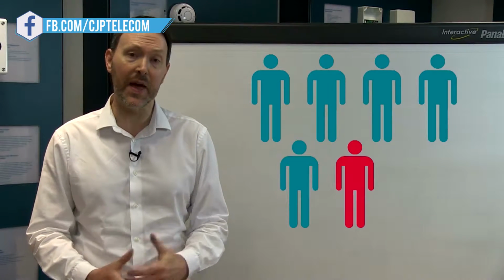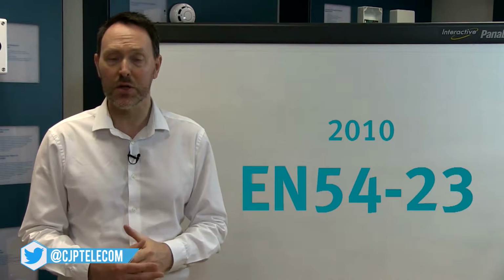1 in 7 people in the UK are deaf or hard of hearing, and they, as well as those who work in noisy environments such as factories, require a visual signal as well as an audio warning in the event of an alarm. Prior to 2010, there was no industry standard to determine the light output that a VAD should emit. Therefore, EN54-23 was introduced to standardise the light output requirement.